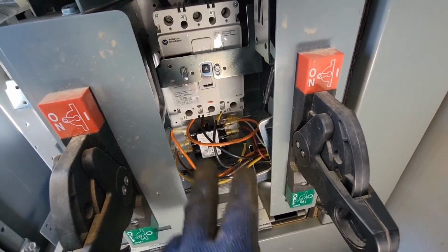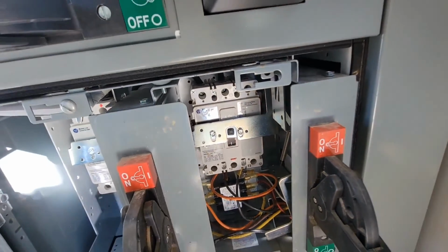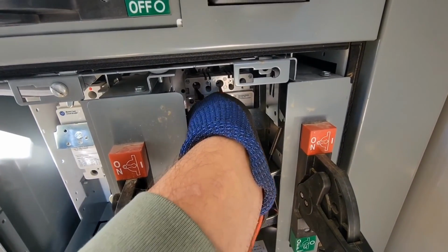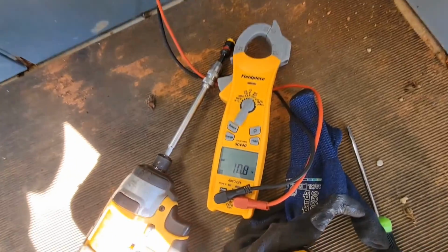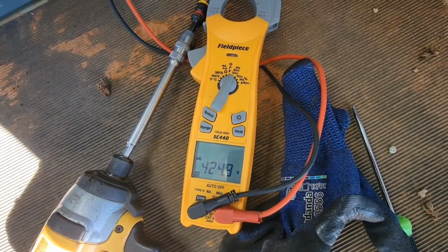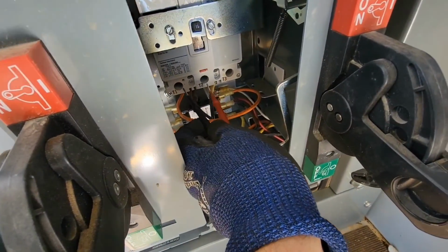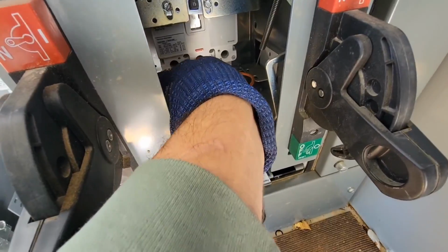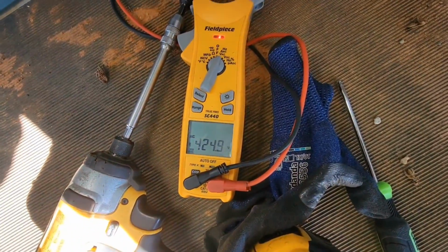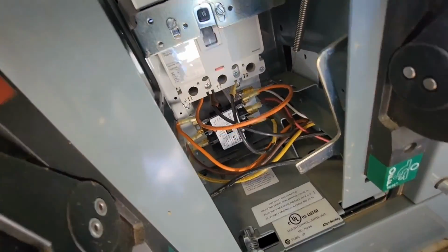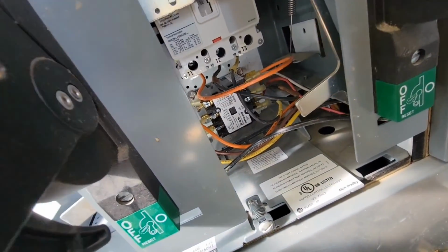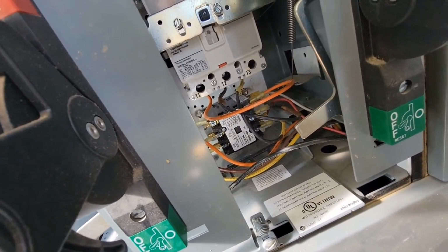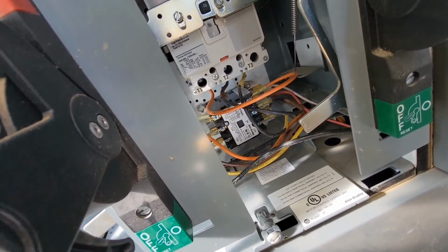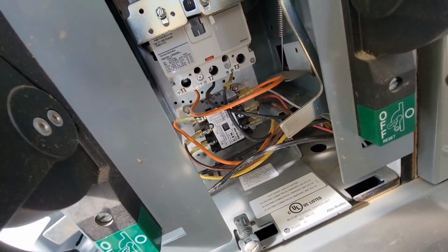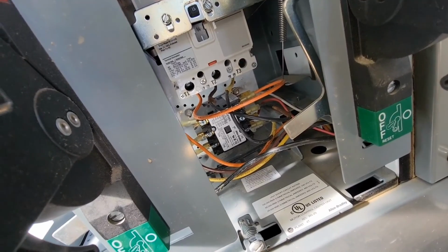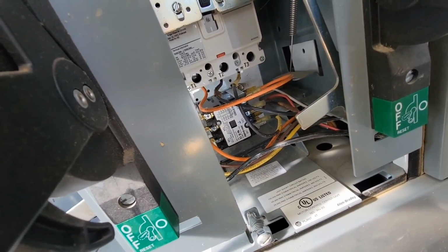Now that we've got it on, let's check voltage across. All right, power comes in on the top. So we're going to check from L1 to L2 and then L3. Got 425 volts. I'm going to check the bottom. That was L1 and L2. We're going to check T1 and T2. 425. I bet you we got voltage, but what we also got is a contactor, and that contactor has a 120 volt coil, and I bet you that's what provides power to that HVAC unit. But I wonder what controls that coil.